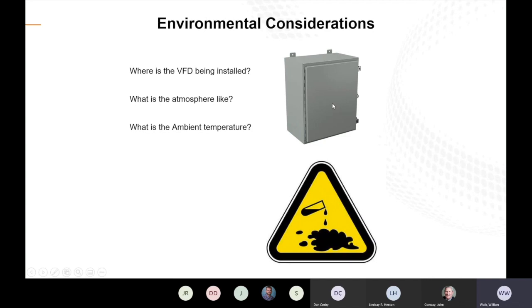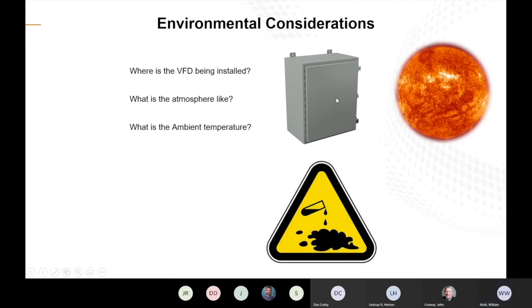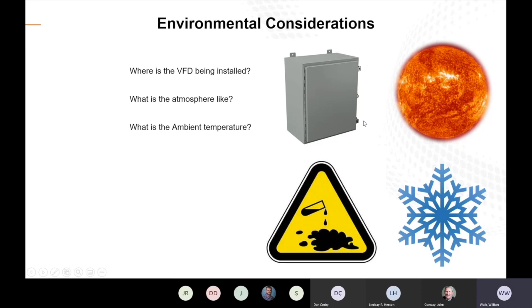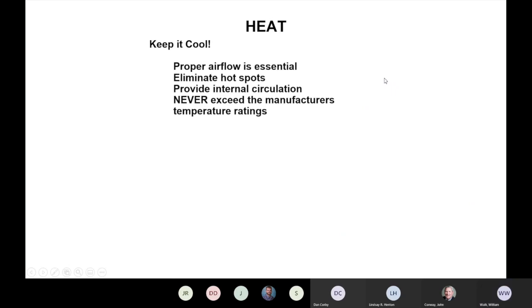And then lastly, what is the ambient temperature like, or the temperatures where this VFD is going to be installed? Is it going to be hot? Is it going to be cold? But with most folks, it's going to be dependent on your heat. So a little bit more reiteration on heat. We want to keep the drive as cool as possible. You want to ensure proper airflow and that we don't have any sort of hot spots.